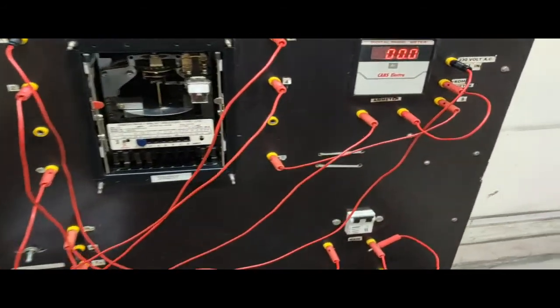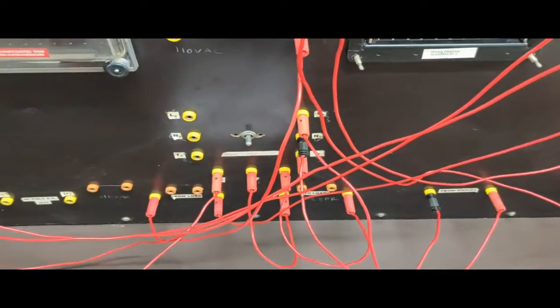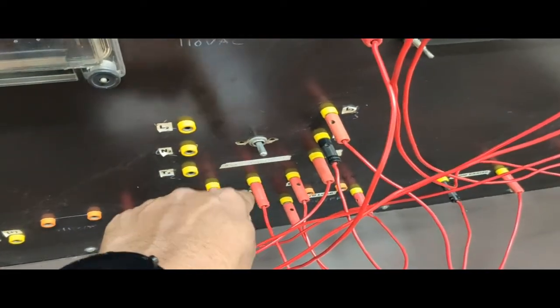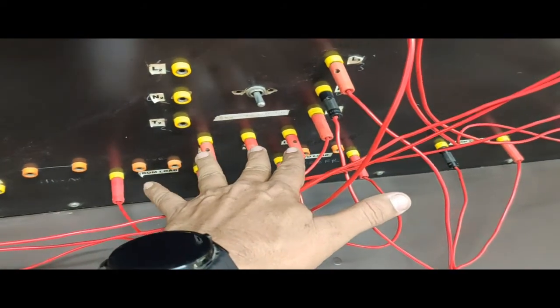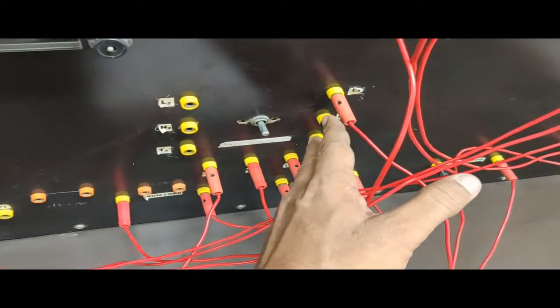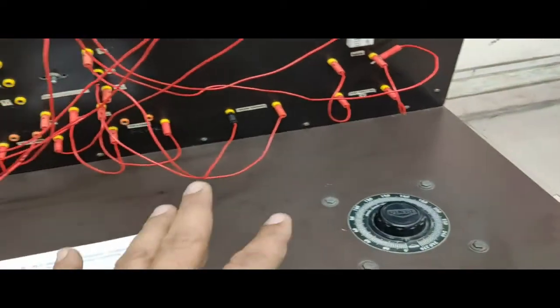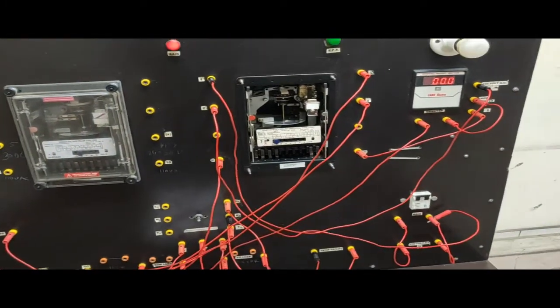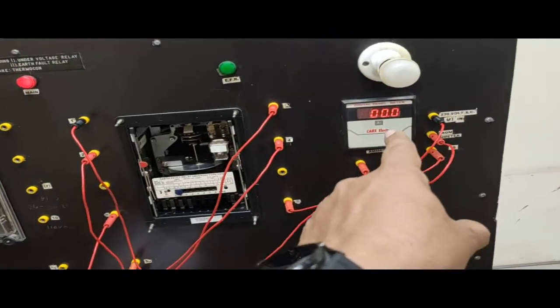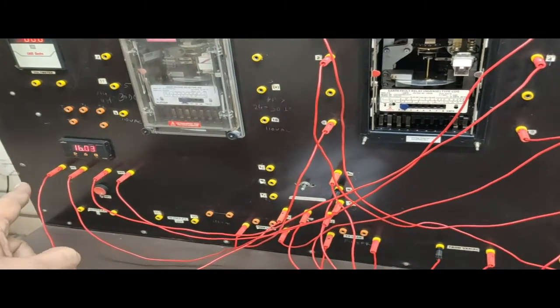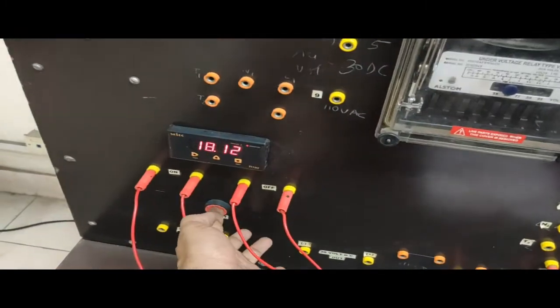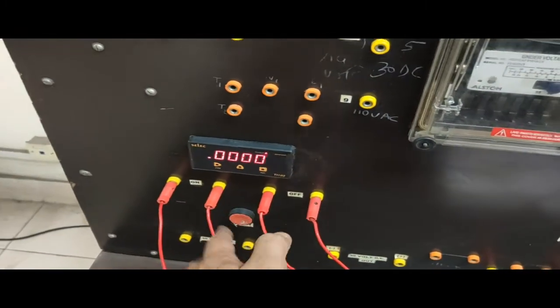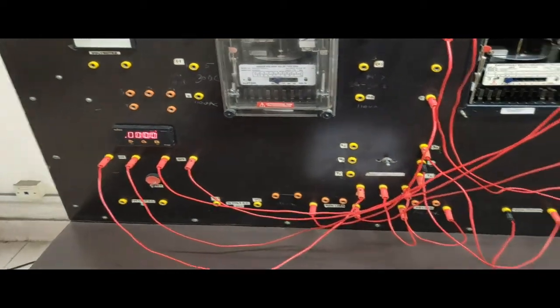So the procedure for this one is that this is the selector switch. If I press the selector switch in the downward position, then these 3 terminals will be short circuited to that one, and the current will flow through that particular relay. So the relay current can be measured by the ammeter, and using the timer. So just to reset the timer. So using the timer we can get the relay operating time.